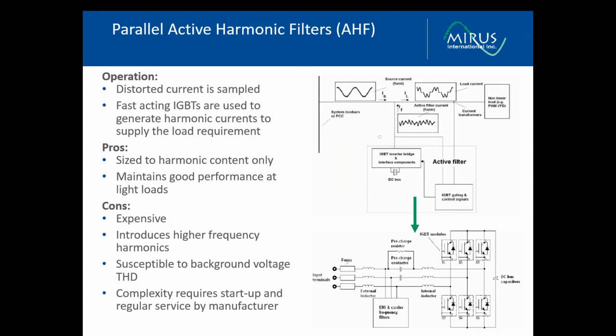These can be reasonably effective, but they can be quite expensive. And one major issue is related to the fact that they'll introduce some higher frequency harmonics based on the IGBT switching frequencies, the IGBTs that are used to create the harmonics to inject back into the power system. They would be susceptible to background voltage distortion, and they're quite complex devices, so require startup and regular maintenance.